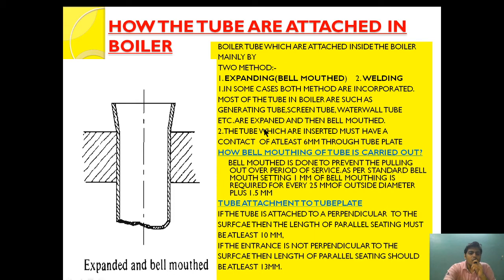These tubes which are inserted must have a contact of at least 6 mm through the tube plate, so that they have a good grip. Now, how is bell mouthing carried out? Bell mouthing is done to prevent the tube from being pulled out during the period of service.